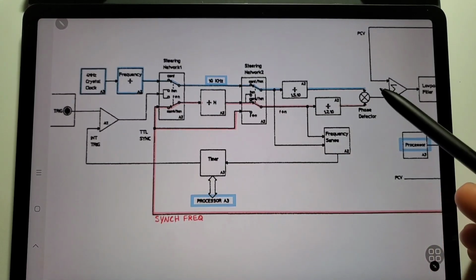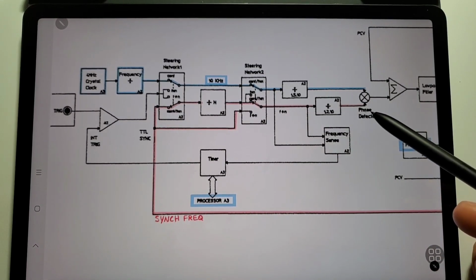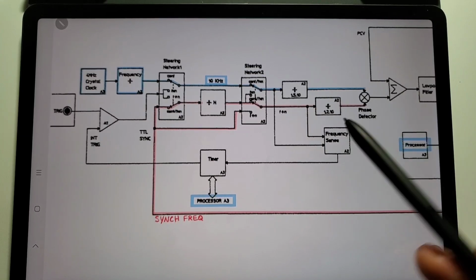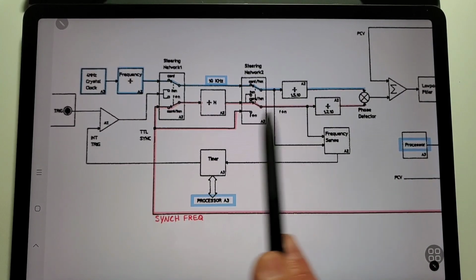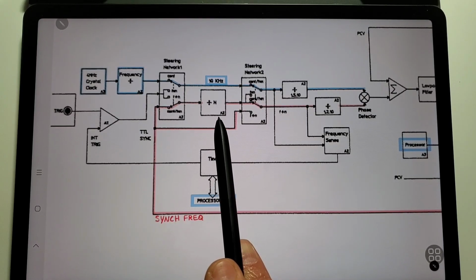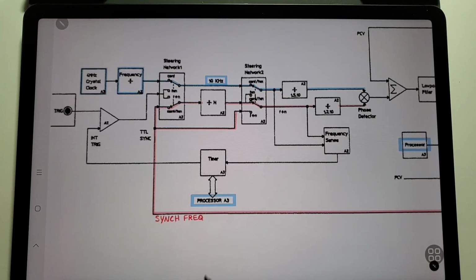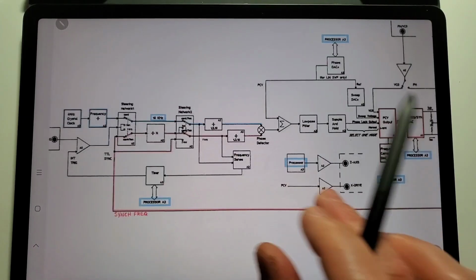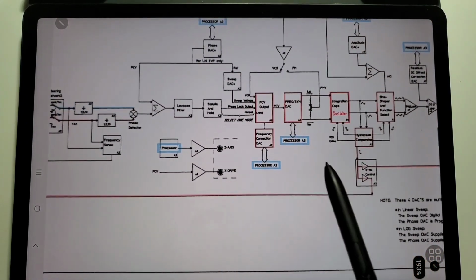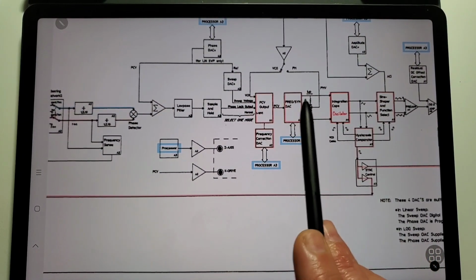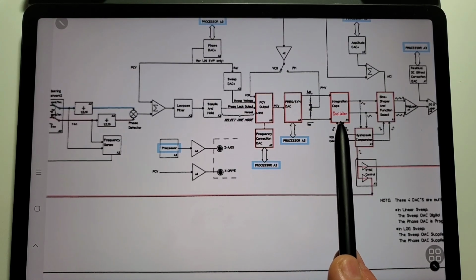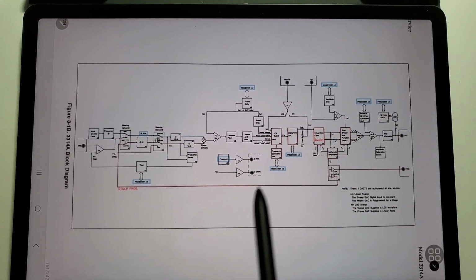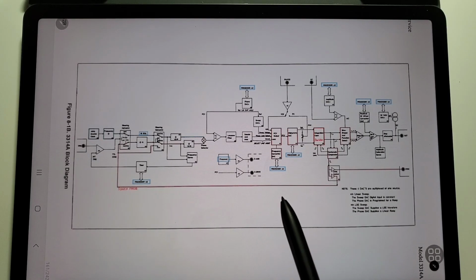And the actual comparing is done by means of phase detection, just like a phase lock loop circuit, with a combination of these frequency dividers as clock multipliers that are programmable by the CPU based on the user selected frequency. Once the difference in frequency or phase has been detected, the amount of correction is ultimately fed back digitally into the DAC chip in order to adjust the current sources feeding into the oscillator in order to bring it into sync. This feedback loop and adjustment may need to be repeated a few times while the CPU controller tries to bring the frequency into lockstep.